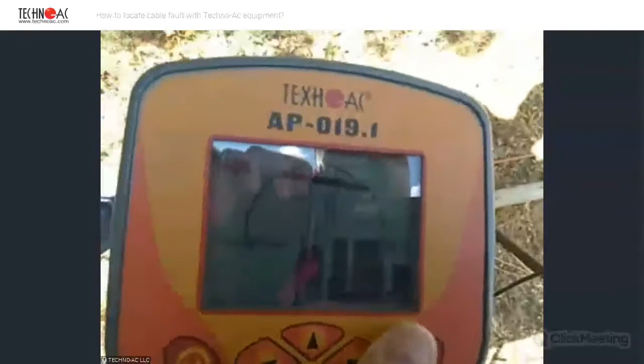You can do the following. You can rotate the sensor and check if there's any signal change, and you will be able to see that you are standing right above the fault. But I recommend to do it in accordance with the cable position. So you just go meter by meter. You're checking the cable meter by meter. You go forward until you find a place where the signal is almost missing. And this is going to be the spot of your cable fault.